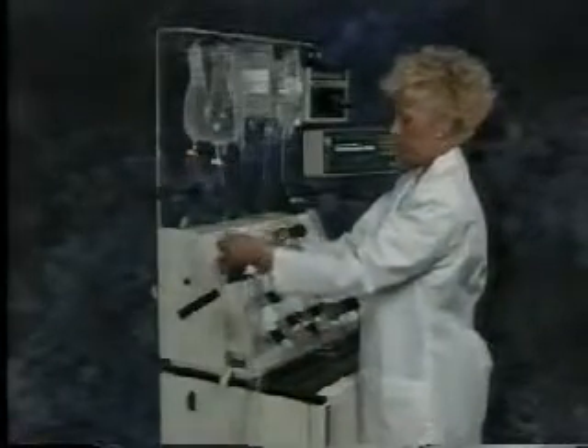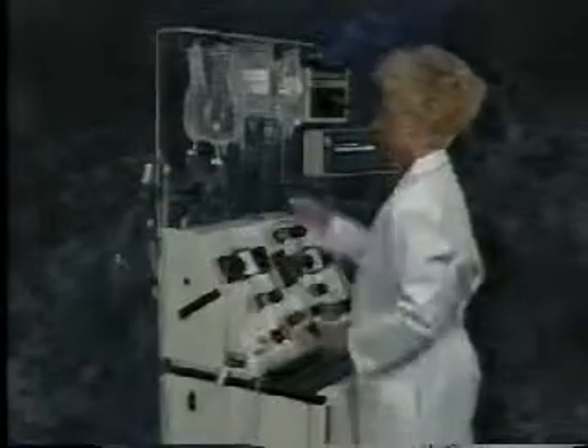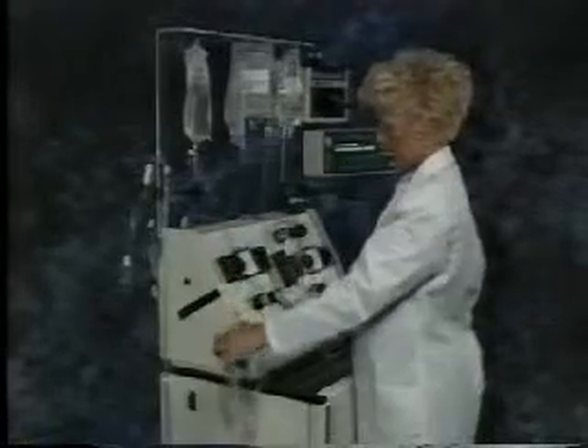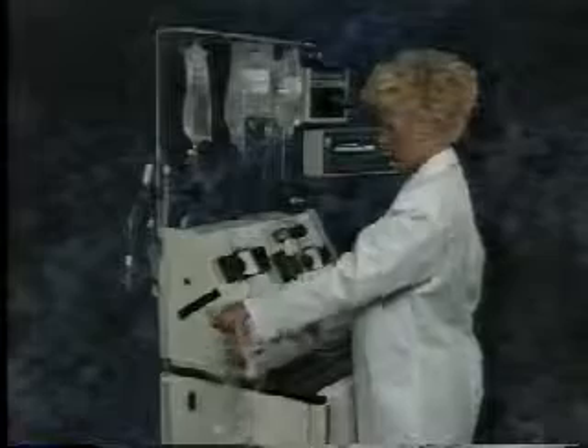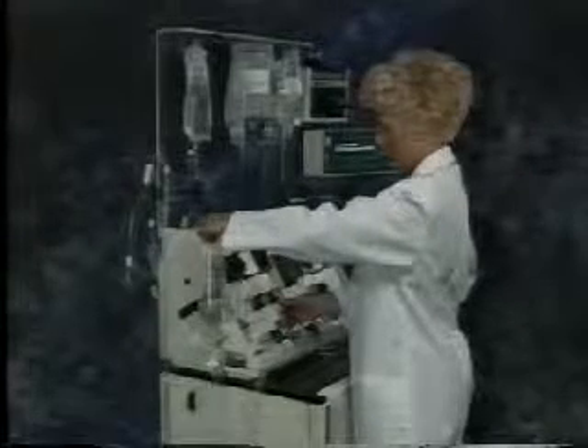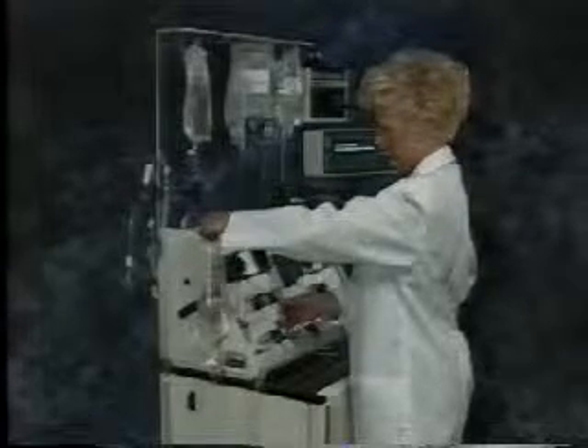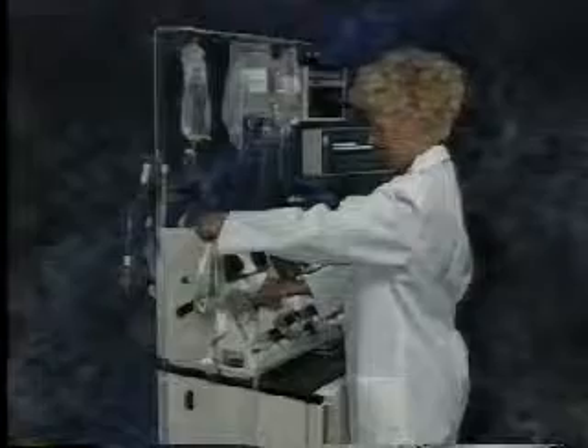Remove the access pressure sensor from its housing. Check that the access line clamp is closed, and check that the access saline roller clamp is open. Lower the saline container until the fluid level in the container is even with the centrifuge cover for about 10 seconds. Next, raise the saline bag until the fluid is level with the access pressure sensor and hold at this level for about 10 seconds. Meanwhile, watch the diaphragm and wait until it is properly positioned. Then, load the access pressure sensor while keeping the saline container even with the sensor. Rehang the saline container and press the Continue key to clear the alarm.